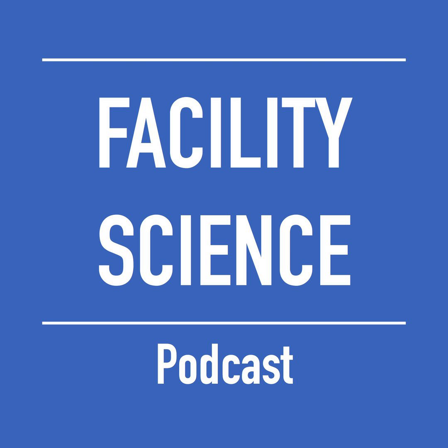Some VAV boxes, and I've seen this, have no provision to access the interior of the box and clean the coil. And so you might have a situation where you're running the system all the time and everything looks fine, but no air is actually getting through the VAV box into the space. The valve is opening and closing just fine and everything looks like it's working, but air is not getting through. And that's because your reheat coil has been clogged up by dust, lint, whatever it is.